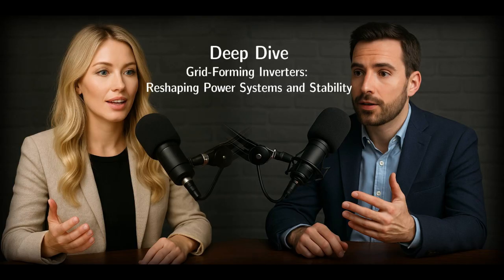Inside the VSM algorithm, they essentially solve the classic swing equation of a synchronous machine, but in software. There's a virtual rotor equation. The change in virtual speed, d omega/dt, is driven by the power imbalance, just like a real machine, but divided by a software-defined inertia constant, H virtual. It's a digital mimic. And what advantages does this digital approach offer over the real thing? Several key advantages. First, the inertia, H virtual, is programmable, adjustable from maybe 2 to 10 seconds, sometimes even dynamically. Second, the response speed is incredibly fast, in sub-second frequency support compared to 10-plus seconds for traditional governors.